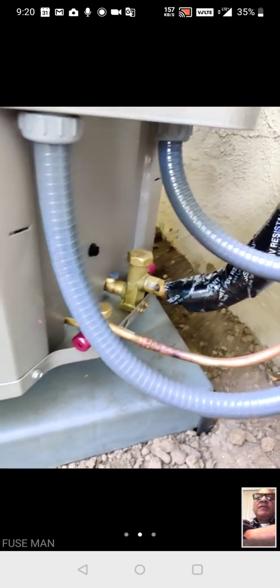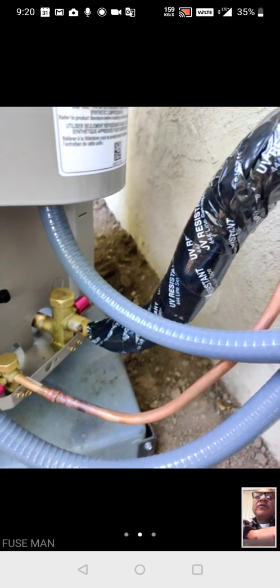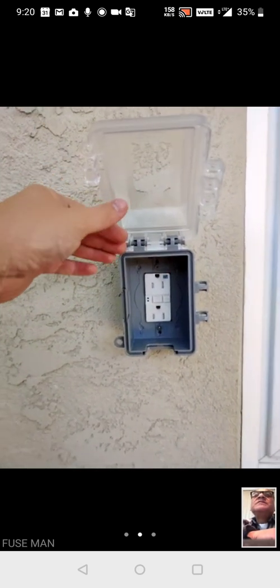Now let's look at the bottom. You have your anti-tamper caps — wonderful. Your stake-down to the ground — I see that, great. There they are at every corner — awesome. Now let's look for the service receptacle. Where is it? Can you open that for me? I just want to see that it's water-resistant.